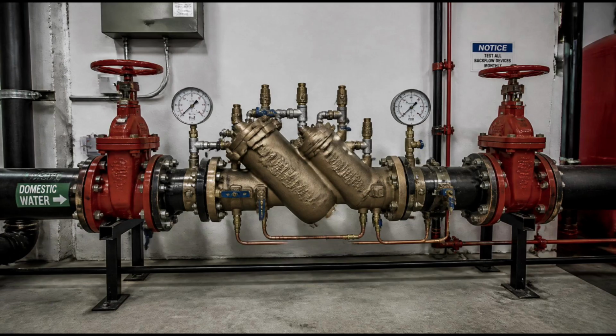The design of the device ensures that if pressure ever reverses, the backflow preventer closes and holds, blocking any backward movement of water before it can reach the municipal main. One of the most common and widely required types in commercial applications is the reduced pressure zone assembly, often referred to simply as an RPZ.